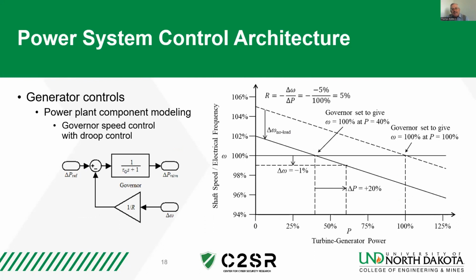The governor has a droop type control. There's a similar one also for voltage regulation. Effectively, as more power is needed in the system, it is drawn from the inertial masses of the generator, causing the speed to droop and indicating to the governor that we need more power. Likewise, we do this with voltage drops to improve our voltage excitation. So there are parallels of both power and voltage in the control system.